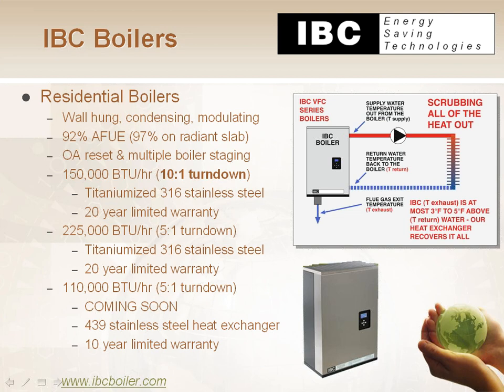He's also kind of cool because even though the AFUE formulas don't reflect this properly, he has very good efficiency, and you can measure that with your combustion analysis meter or temperature gauge. The exhaust temperature coming out of the stack of that boiler is never more than 5 degrees warmer than the return water coming back to that heat exchanger. A normal boiler might be 30 or 40 degrees warmer. This guy at most is going to be 5 degrees. So if you're not sending energy out the exhaust, that basically means by definition you're keeping it in the building. So hopefully the AFUE formulas catch up to that technology and reflect it a little better soon here.